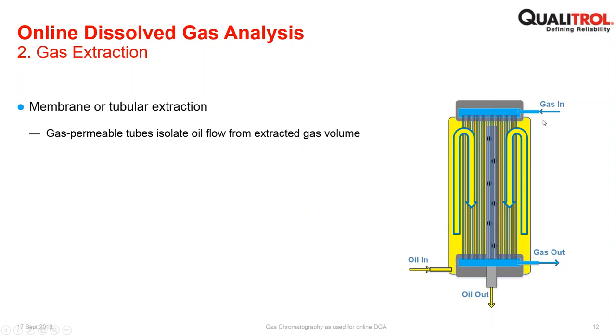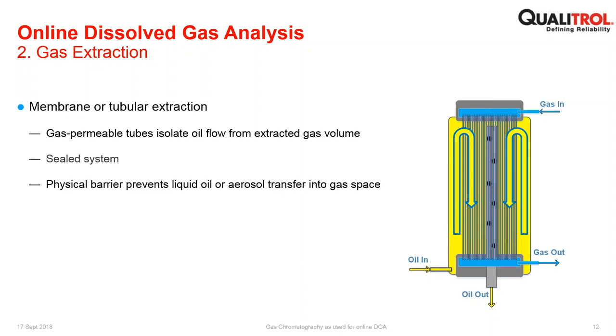The big benefit of using this type of system is that you do not put the oil in contact with the atmosphere. So the oil does not get an opportunity to absorb any of the atmospheric gases, carbon dioxide, oxygen, nitrogen, and indeed moisture. By keeping it isolated in this tubular membrane extraction system, the oil that goes back into the transformer is not contaminated with atmospheric gases. It's a sealed system, and that physical barrier prevents liquid oil or aerosol transfer into the gas phase, but it also prevents atmospheric air from going into the oil.